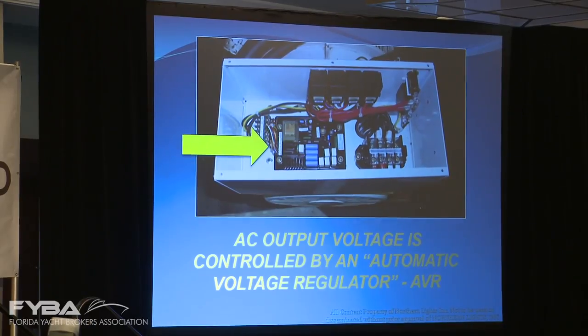Many years ago, we had generators that didn't require automatic voltage regulators — they were self-regulating. That was a little simpler, and that's a good thing, but you don't get something for nothing. When you applied a large load to a self-regulating generator, you'd get a pretty big voltage dip and a pretty good voltage spike. So in the last decade or two, as electronics came along, we found it was really necessary to control the voltage a lot closer, so as not to blow up somebody's expensive electronics.